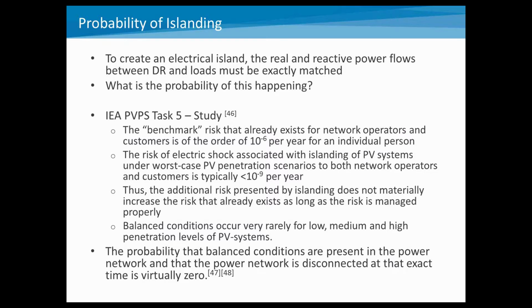When you separate into an unintentional island system, if you have a small amount of distributed generation, you most likely won't be able to maintain an island condition. And if you have an overabundance of distributed generation, again, it'll be difficult to maintain that island without moving outside the voltage and frequency nominal set points.